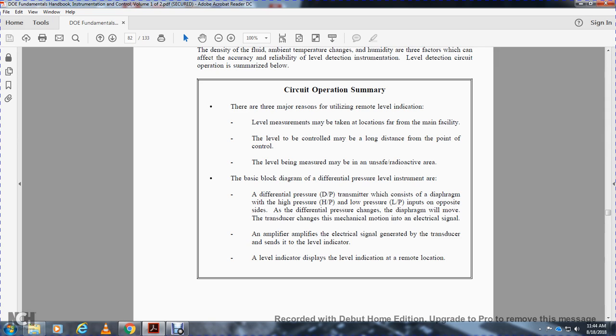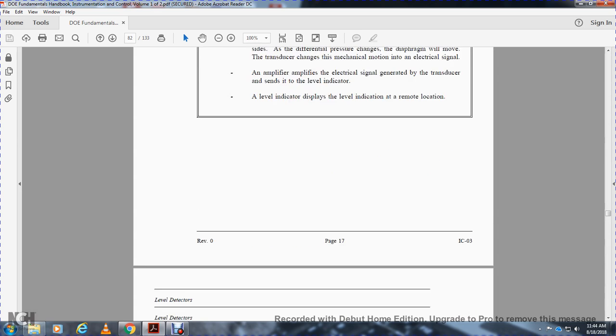Basic block diagram, differential pressure level instrument with the differential pressure transmitter with the diaphragm, high pressure and low pressure inputs, and output. With the differential pressure change, the diaphragm will move the transducer, changing the mechanical motion into an electrical signal. The amplifier amplifies the electrical signal generated by the transducer and sends it to the level indicator display at a remote location.